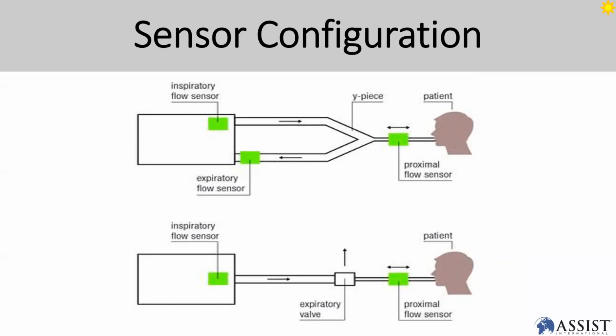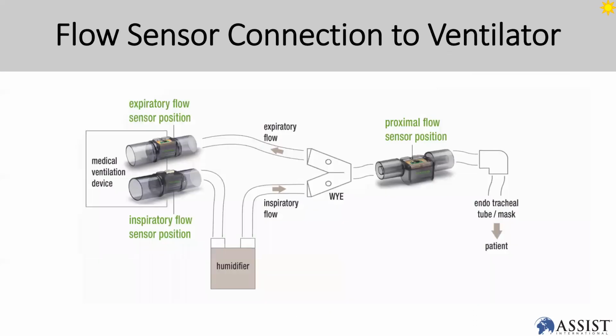But inspiratory flow and expiratory flow sensors are very common that you're going to see on some of your ICU ventilators. On some you only have inspiratory flow, but you don't have an expiratory flow sensor, but you have an expiratory pressure sensor. So this is the common sensor that you're going to see on the ventilator. Sometimes you're not going to see a proximal flow sensor at all, but you're going to commonly see expiratory flow and inspiratory with the humidifier connected. This is a Y connection type of patient circuit. So this is another method that you're going to see.